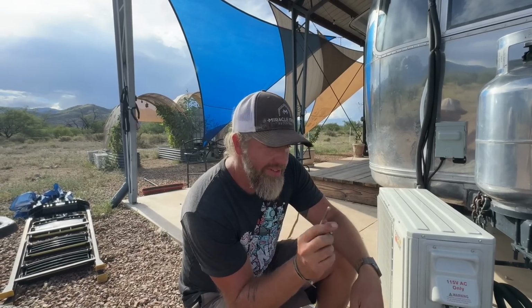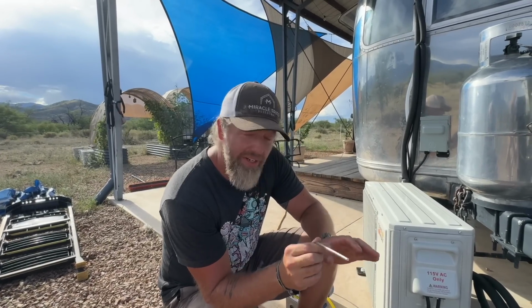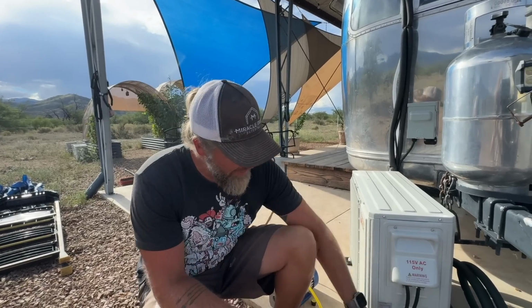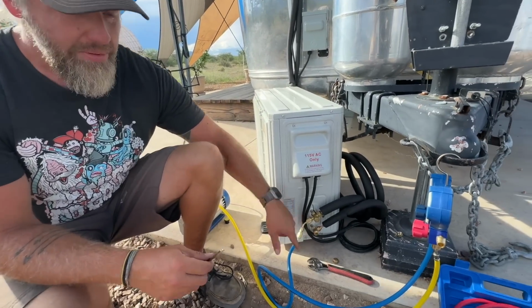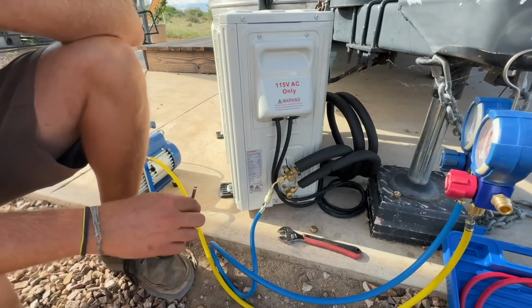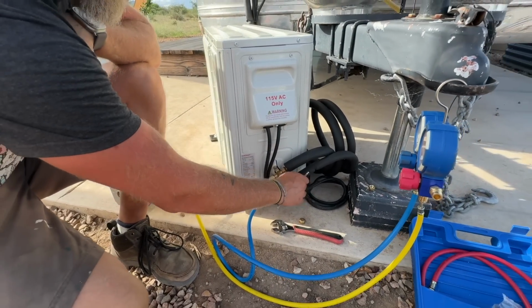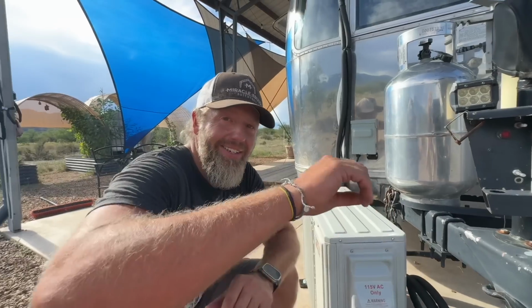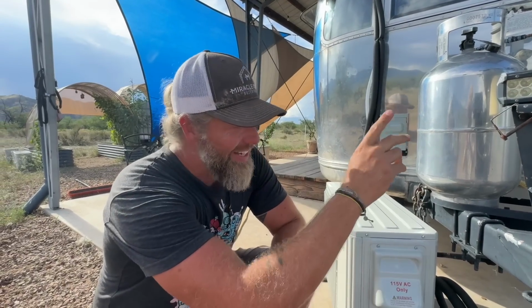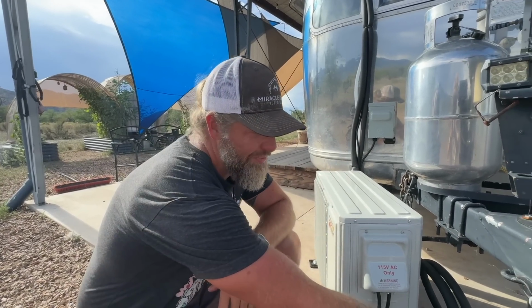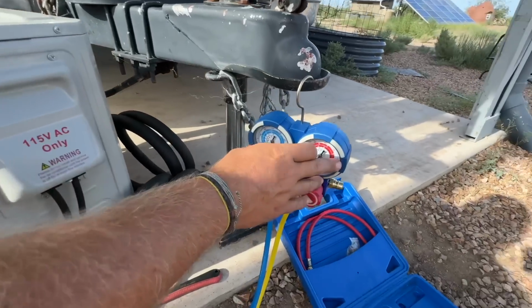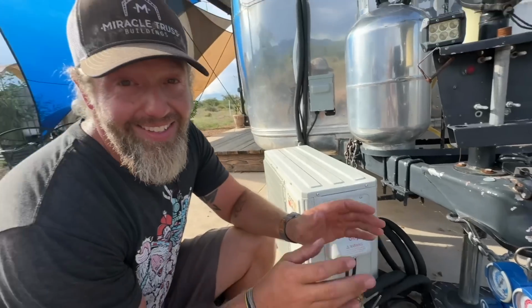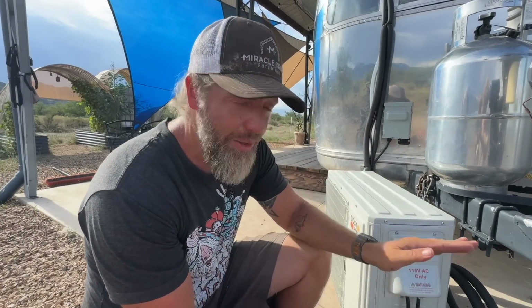So the good news is the negative pressure held. Next we go to the liquid side, the small copper pipe. We open the service port and turn it a quarter turn for 5 seconds. That lets a little bit into the inside unit, you'll hear a rush, and on the manifold gauge it'll pop up to a positive pressure. This is the second leak test, we let it rise to positive pressure, not using all the refrigerant, just some of it, then let it hold for another 5 minutes to make sure there's no leak.